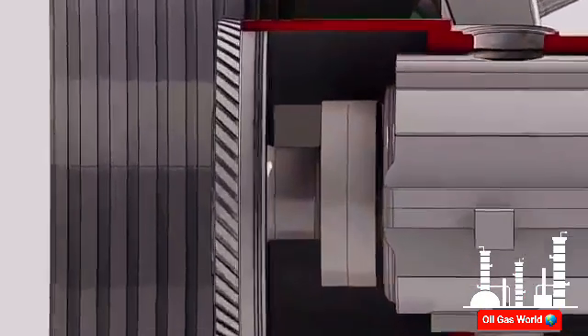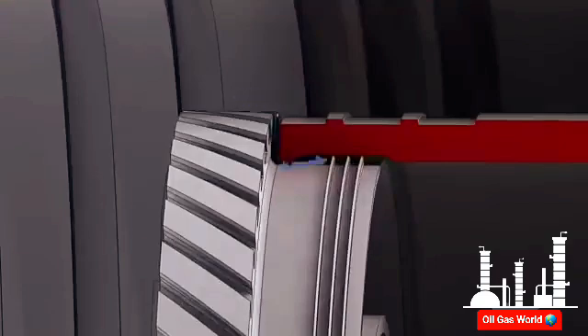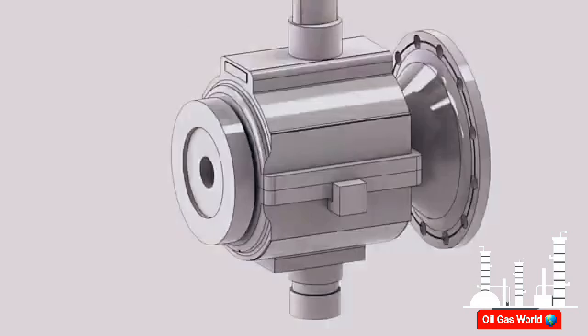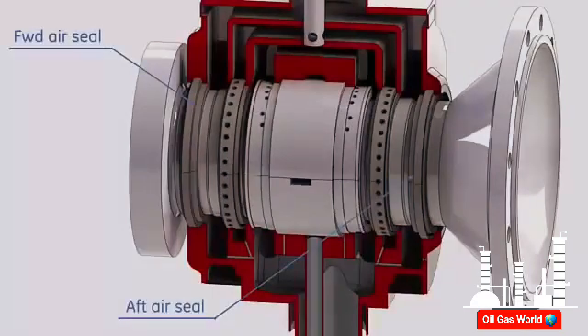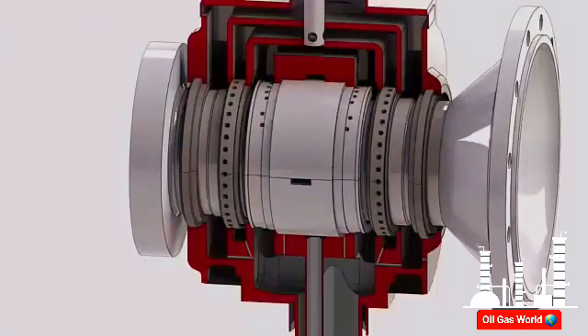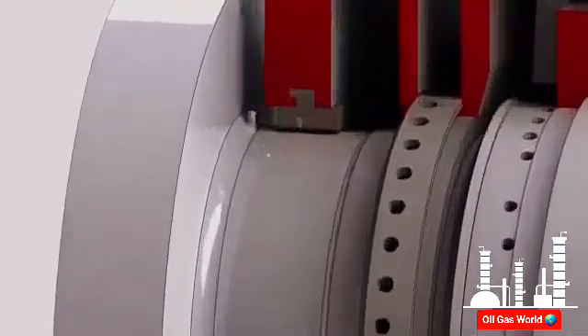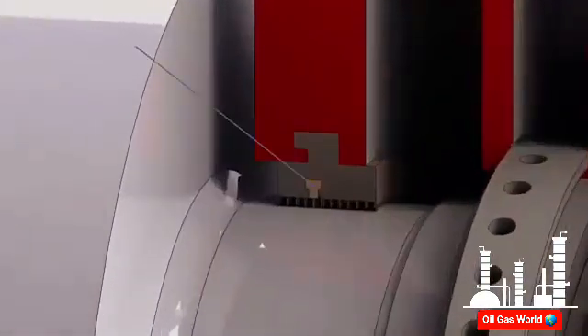Bearing 2 is located in a pressurized area between the compressor and the turbine. This compressed air is leaking from the high-pressure packing at the aft end of the compressor shaft. Labyrinth seals are installed on both ends of the housing to prevent this air from leaking inside the housing. Since any air leakage past these seals doesn't perform any additional work, any reduction in this flow will result in an increase in the unit performance.